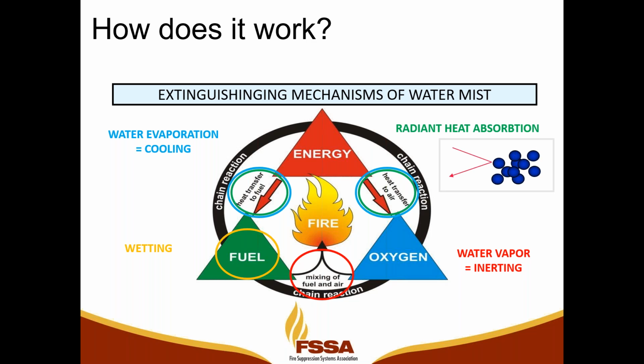And then finally, with water mist systems, you're creating a radiant heat blanket almost. Think of it like a foggy day, right? The sun's always out above the clouds, but as the fog burns off, you can start feeling more heat of the sun. Well, what the radiant heat absorption of a water mist system does is absorb the heat being given off from the fire and not allow it to necessarily roll off the ceiling and activate multiple sprinkler heads that don't need to be activated, because you can control the particular fire with the water mist system using one, maybe two heads for that area, instead of having to discharge maybe 8 to 12 heads on a traditional sprinkler type system to do the same thing. Next slide.